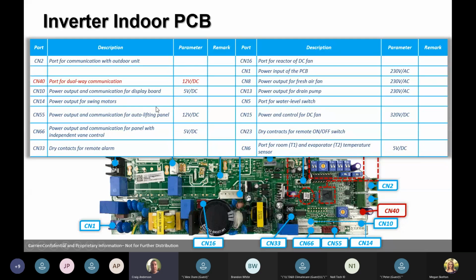In the manual, it's going to tell you too, on your CN40, that should be 12 volts going to that piece of equipment, whether it's your sensor, reversing valve, or whatever it is hooked up to. It gives you an idea of what kind of power you should be testing. So always look for those CN numbers on your wiring diagram of your unit to do your future testing.